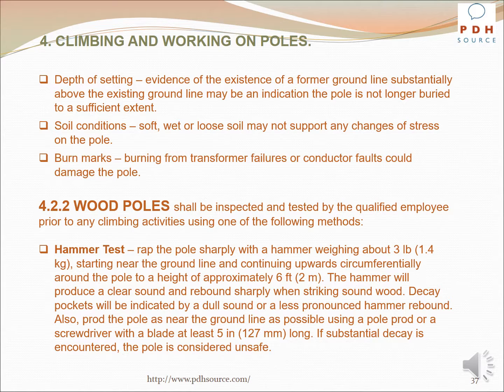Wood poles should be inspected and tested by the qualified employee prior to any climbing activities using one of the following methods. The hammer test. Rap the pole sharply with a hammer weighing about 3 pounds, starting near the ground line and continuing upwards circumferentially around the pole to a height of approximately 6 feet. The hammer will produce a clear sound and rebound sharply when striking sound wood. Decay pockets will be indicated by a dull sound or a less pronounced hammer rebound.